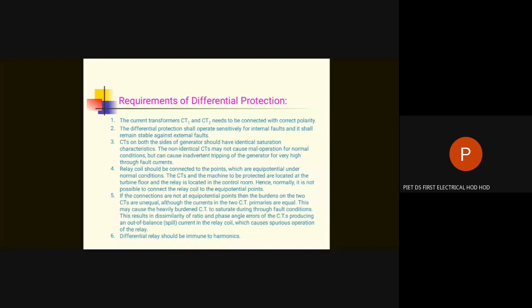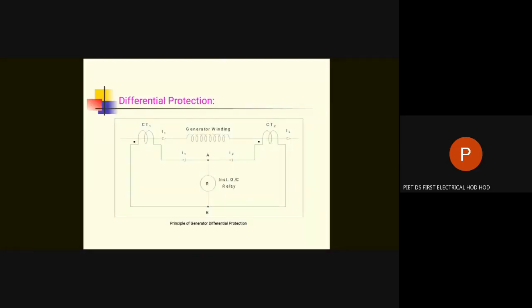Another requirement is this, that the points A and B, as shown in the slide, I hope you are seeing the slide in front of you on your screen, A and B are the points. They should be equipotential, that is VAB, the voltage between A and B, should be zero. This is also not possible because physically the relay is in the control room, the CT is on the turbine floor, and there are CT1 to relay and CT2 to relay connections. For A and B to be equipotential, the distance from CT1 to relay and CT2 to relay has to be the same, which is just not possible because of the geography of the power plant, and therefore points A and B cannot be equipotential, and because they are not equipotential, current will pass through them, and mal-operation of the differential protective system can occur.